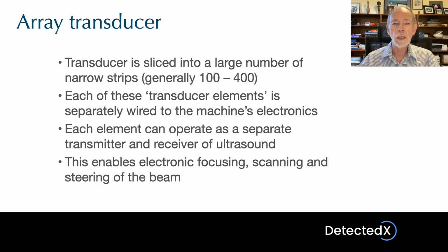An array transducer is simply a transducer that's been sliced up into a large number of identical narrow strips. Generally, there will be somewhere between 100 and 400 of these strips in a single transducer. Given that the transducer is only a few centimeters in length at most, this means that the strips are obviously very narrow. Every single one of these strips, which we refer to as transducer elements, is separately wired up to the electronics in the probe and therefore can be connected to the machine's electronics.